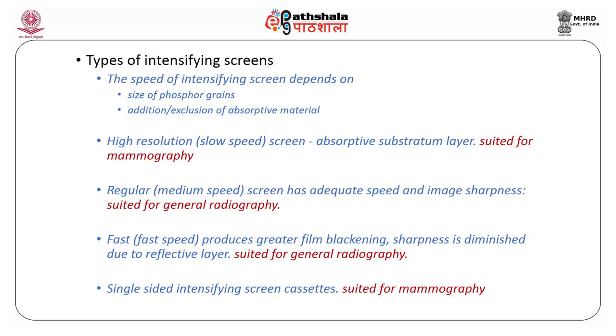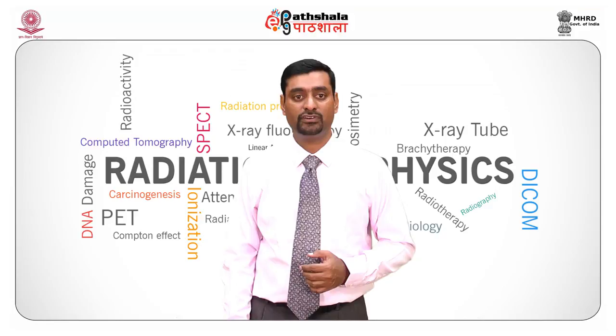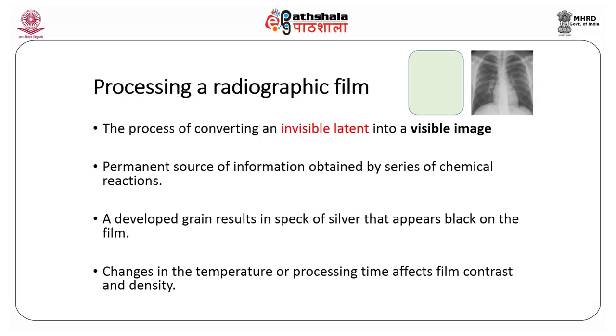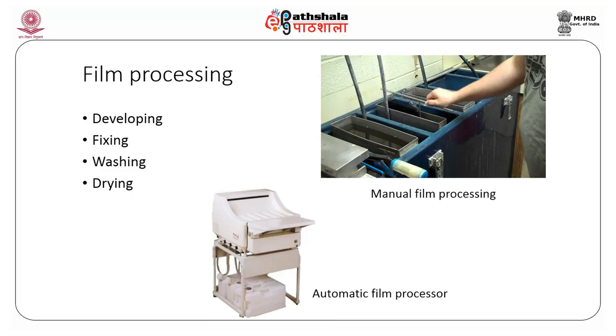Next we move on to the processing of the radiographic film. The process of converting the invisible latent image into a visible image is called processing. It is a permanent source of information obtained by a series of chemical reactions. The developed grain results in a speck of silver that appears black on the film. Changes in temperature and processing time affect film contrast and density. Film processing has four steps: developing, fixing, washing, and drying.